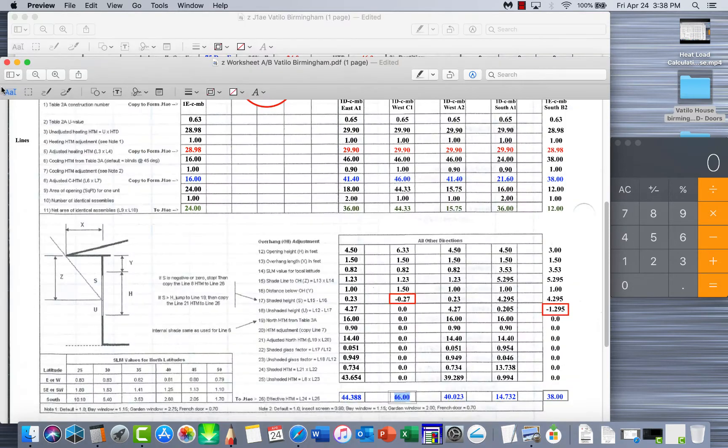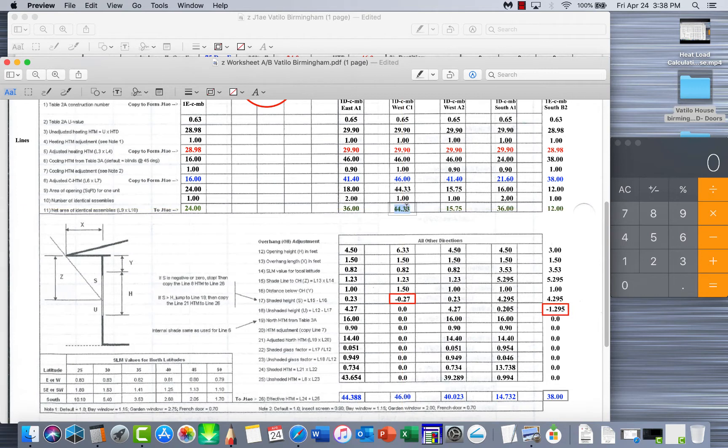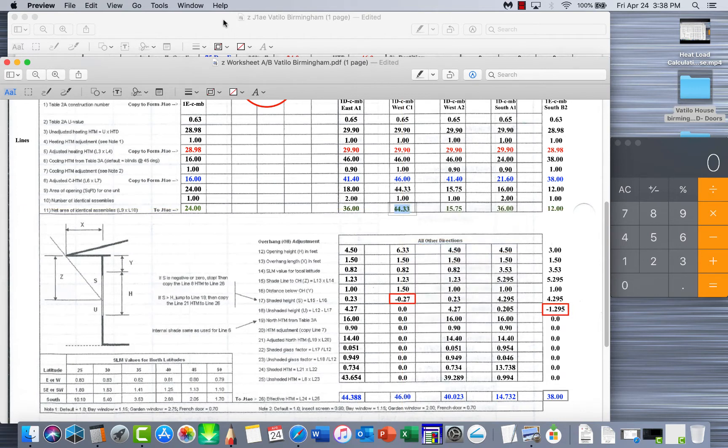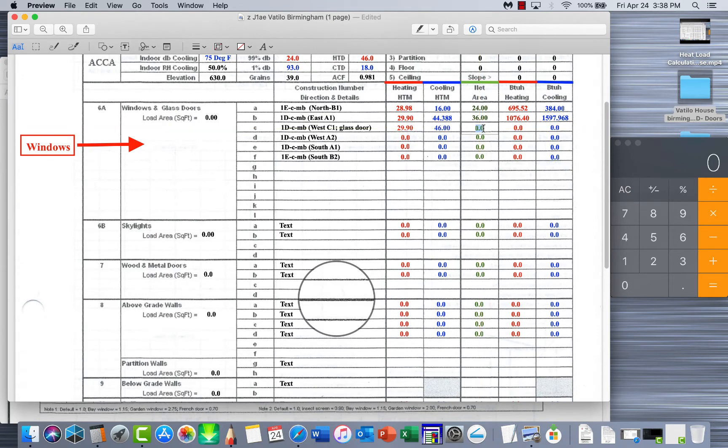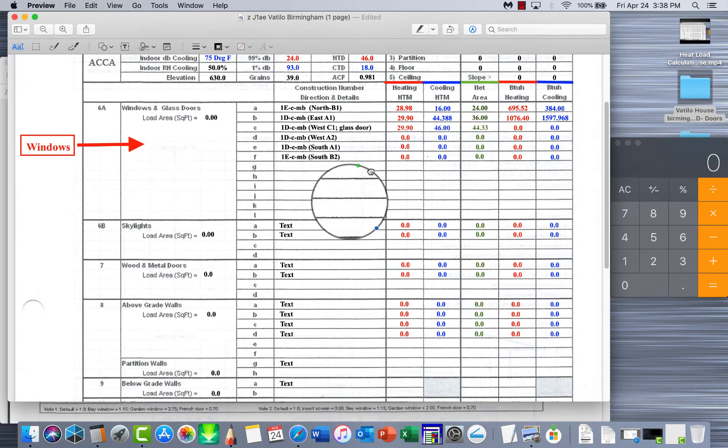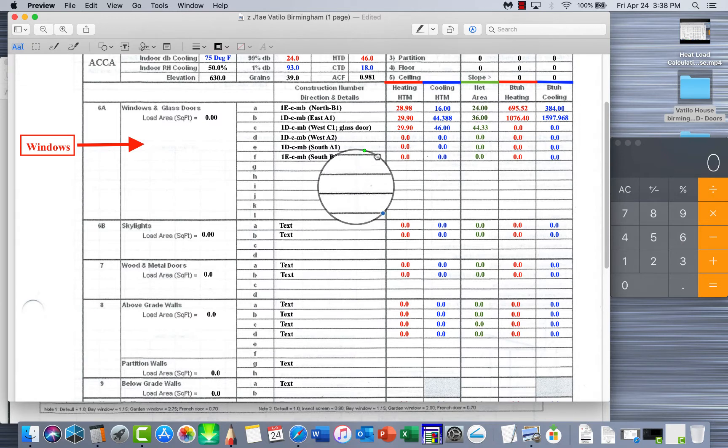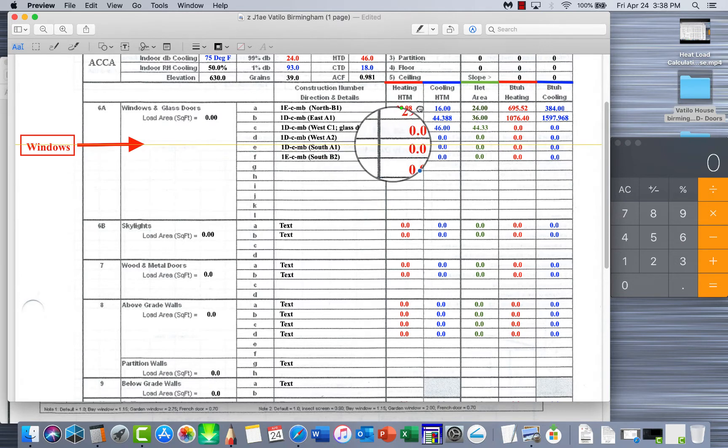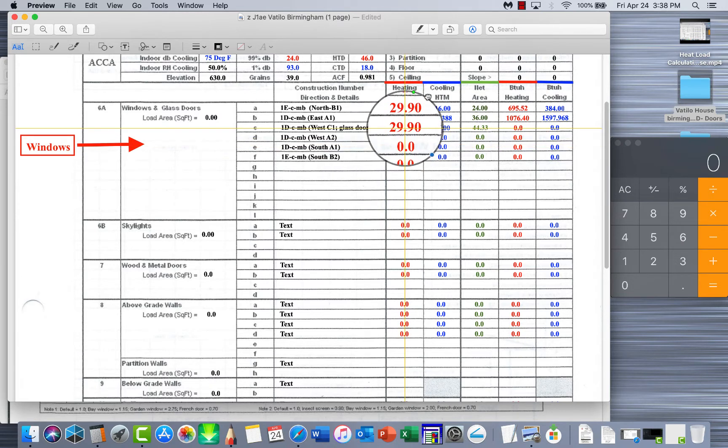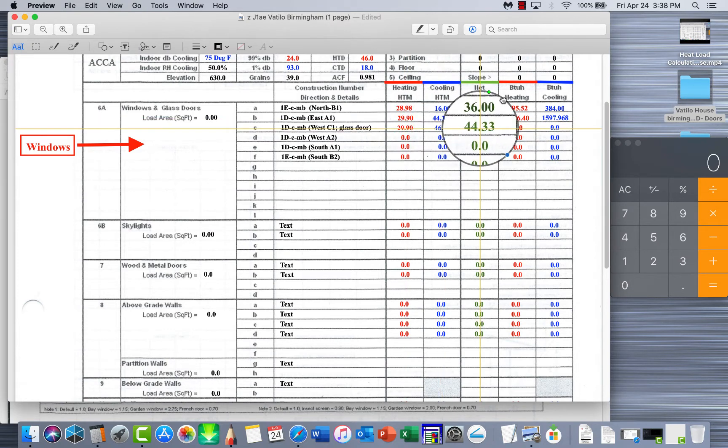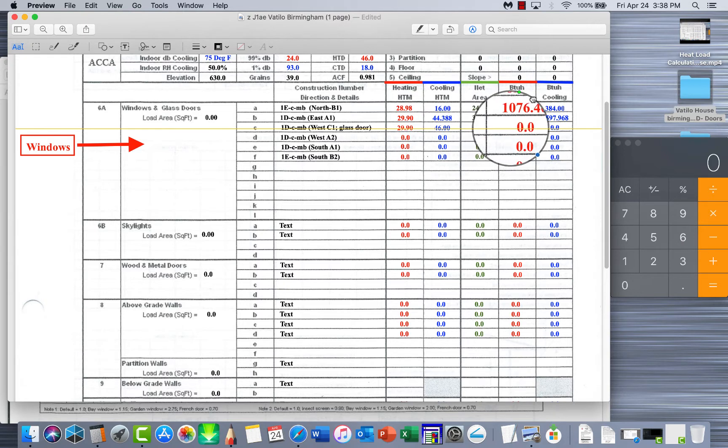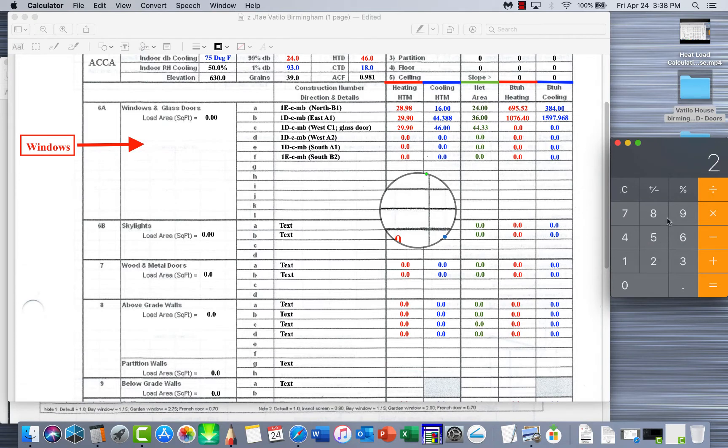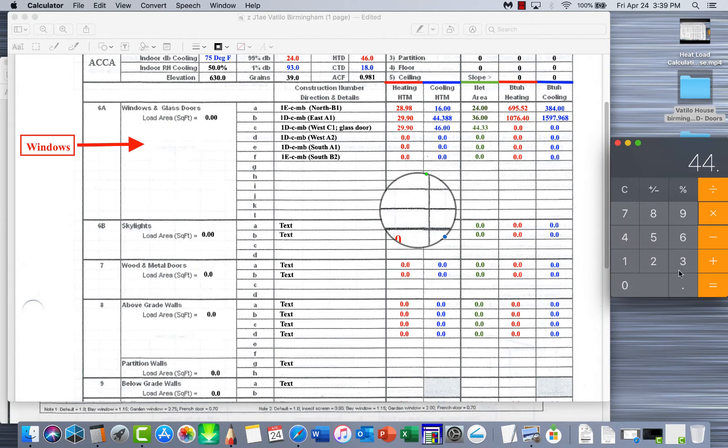Now as always we need to do the heat and cooling BTU load of this. Remember this is based on one hour, so per hour this is how many BTUs that window is going to actually cost you. We'll start with the heating HTM, we're going to multiply it times our actual square footage to give you that. And remember this is all in square footage.